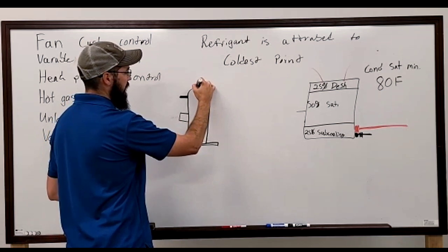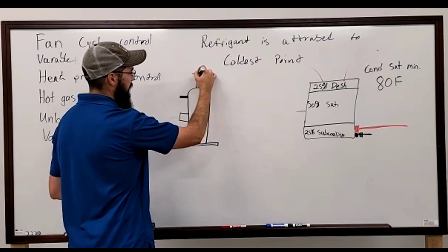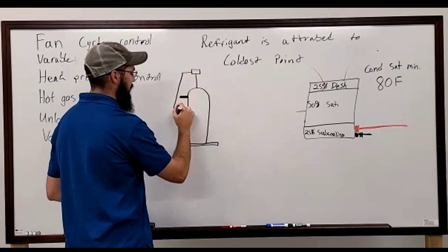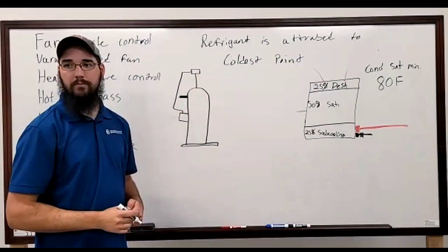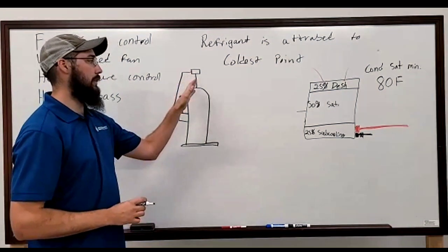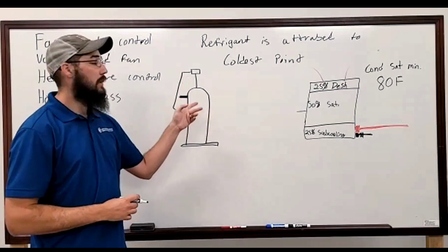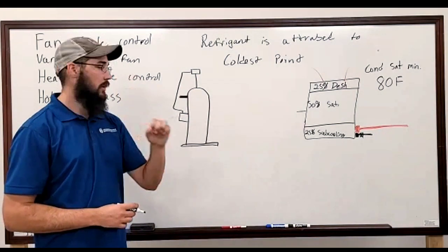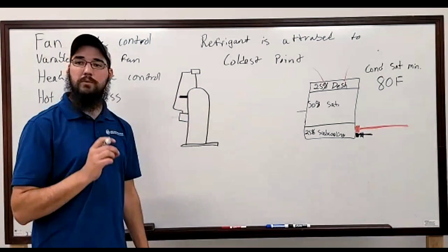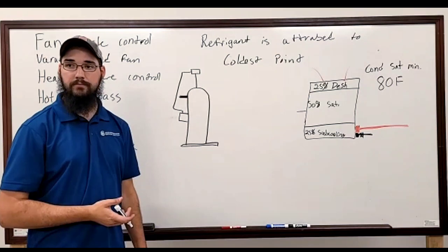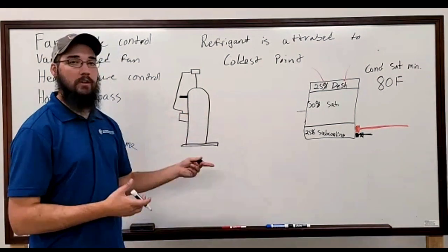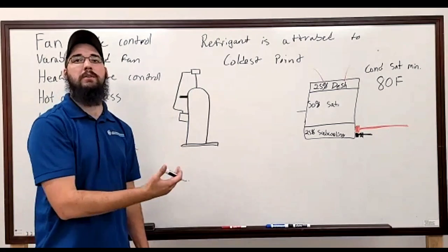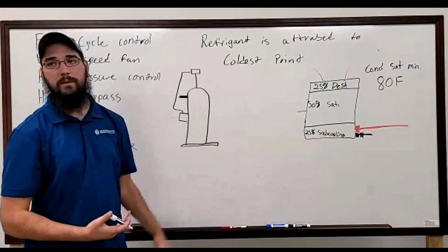They'll have something that looks kind of like this, a little tube coming off. They'll have a solenoid valve on top, and then it will come down and dump back into the suction line. Okay. That is an external unloader on a scroll. And these are very specifically designed with something like a fixed orifice, if you will, so that it'll reduce the refrigerant volume being moved by 50%, not 100%. And you'll see that your amps drop with it. So you're not completely bypassing all flow. At that point, you might as well turn the thing off. No, we're actually limiting how much flow it's able to send by sending some of that flow back through.